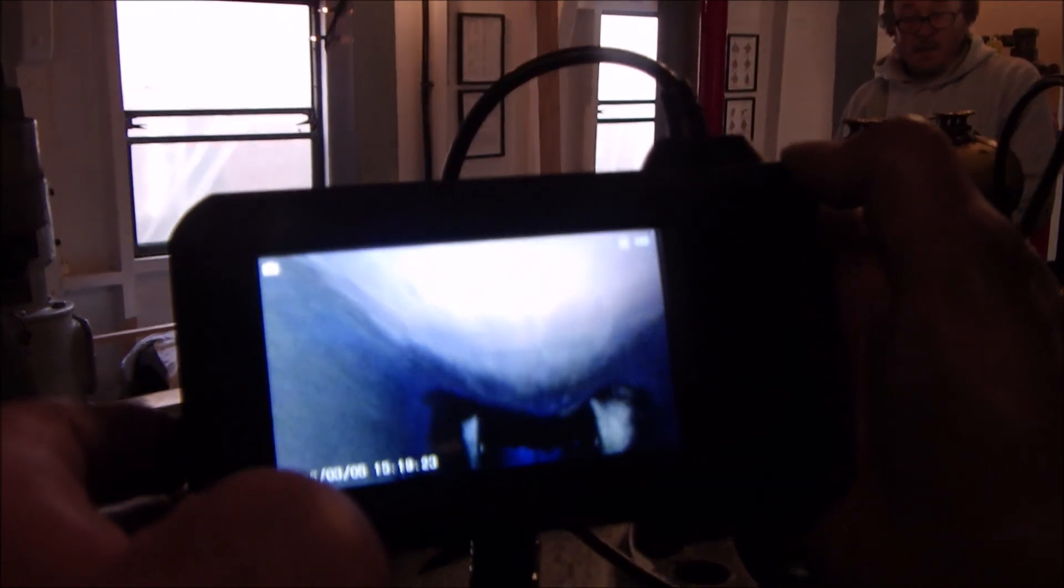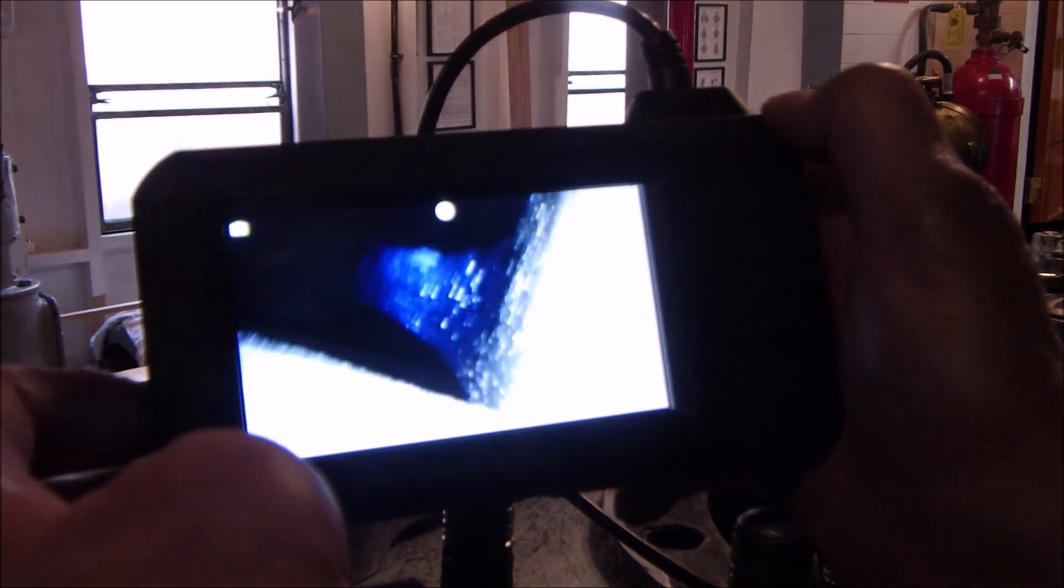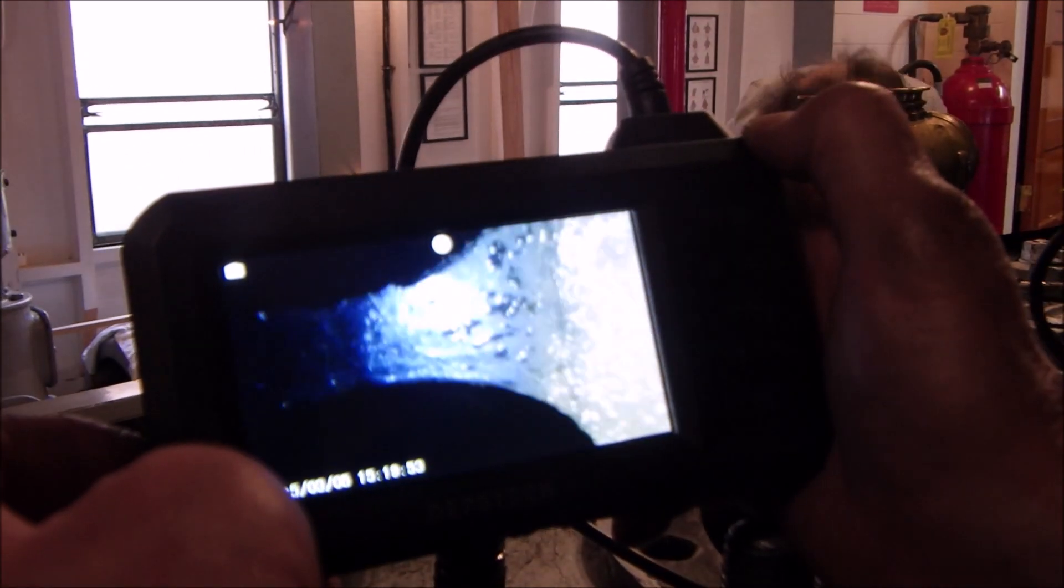So there you can see the top of the IP valve piston. And then this channel would take steam into the cylinder. I think this might be the exhaust from the HP. And we're looking to see if there's any debris, making sure there's nothing that might get sucked into the pistons. This boroscope was the best $115 I've spent. I mean there's no other way to look down there.